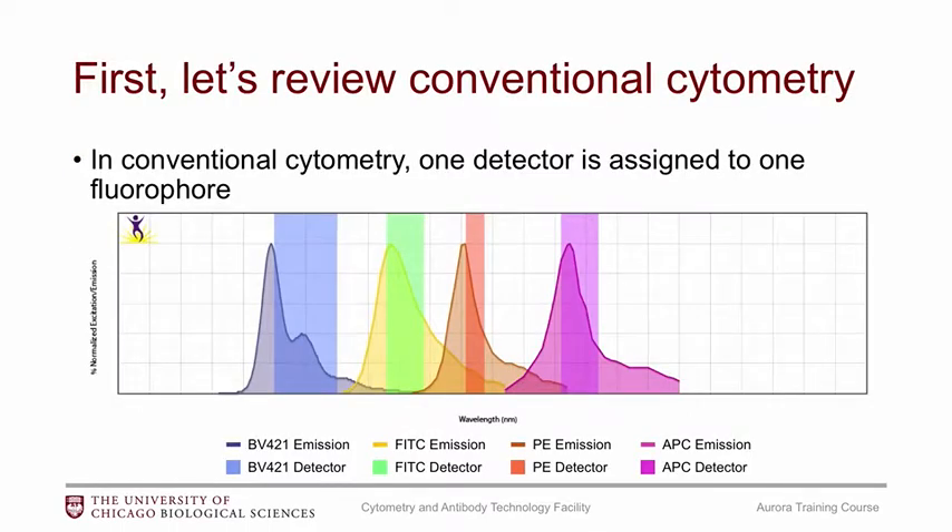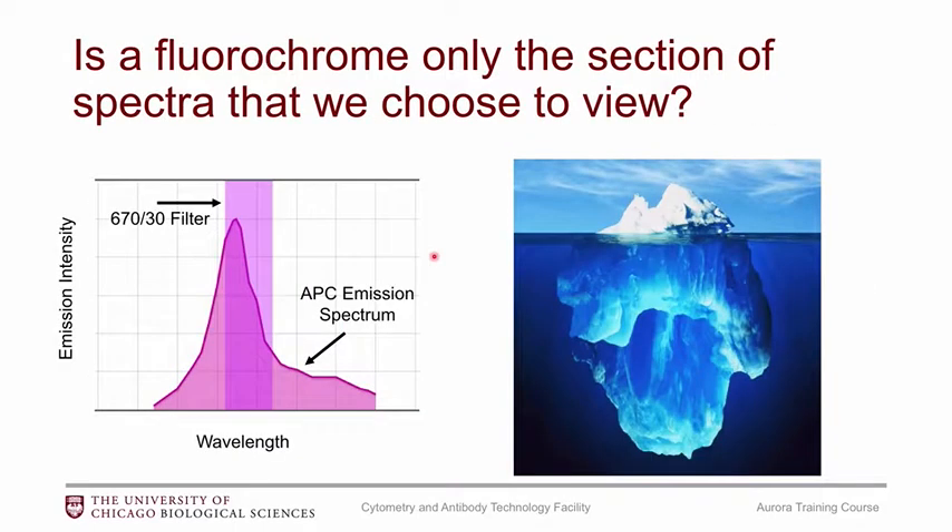The main thing with conventional flow cytometry is that we have one detector assigned to one fluorophore. You can see here the emission spectra of BV421 in blue, and this rectangle represents the detector for that fluorophore. We also have the same for FITC, PE, and APC — one fluorophore, one detector. The issue is that this filter set doesn't actually capture the entire emission spectra of the fluorophore, so we're missing out on some data. Cytek likes to use the iceberg analogy — we're really only capturing the tip of the iceberg.